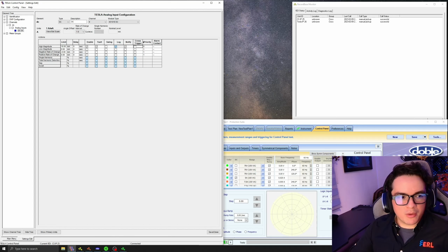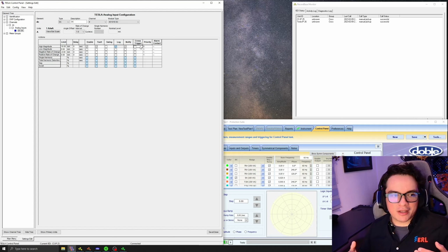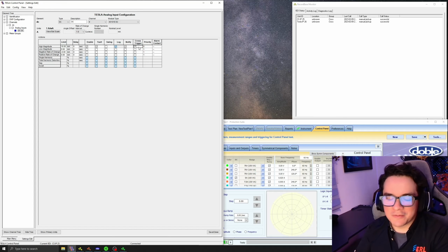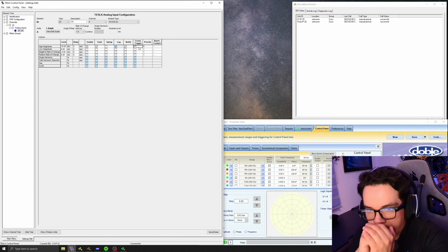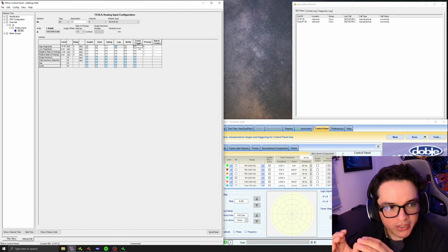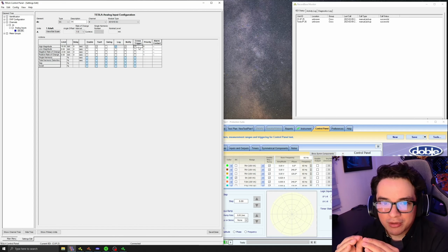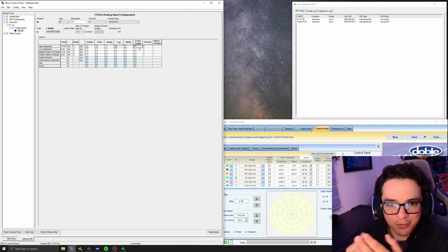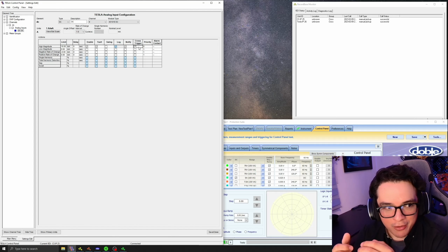But you may be wondering, what is this cross-triggering column we have here? Well, this is a different type of cross-triggering, if we could say that. This is going to be a local cross-trigger. And if you see that the Tesla has up to 8 output contacts, then number 4 is going to be designated for a cross-triggering action. If I were to select this checkbox, then the output contact number 4 is going to be closing, and then we can use that as a digital output to send it over to somewhere else, let's say another Tesla 4000, where we're going to use it as a digital input to create a record.